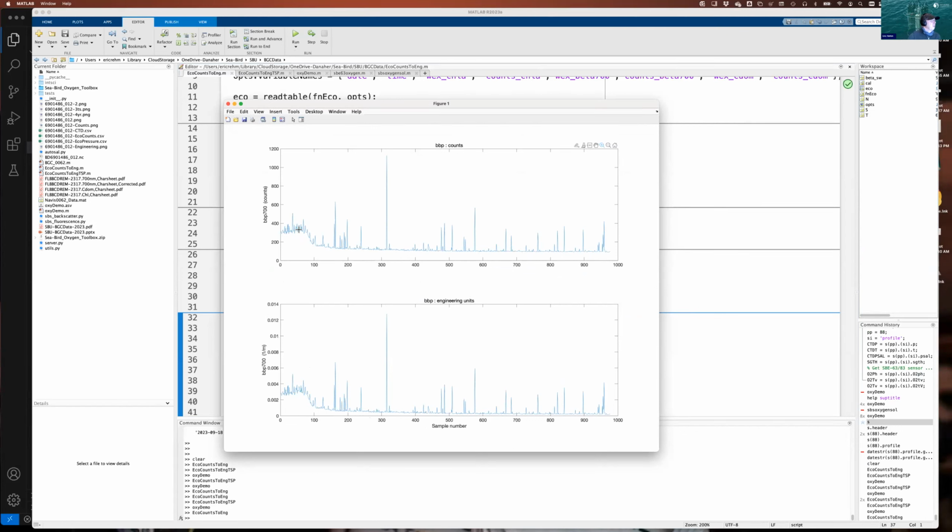If we had 2 different eco units with backscattering, these number of counts might be slightly different due to differences in a resistor or an LED. It's the process of our calibration and those calibration coefficients that guarantees that, whatever changes there are from instrument to instrument, you would always get the same number. So our goal is that if we had 1, 2, or 20 eco fluorometers that had backscattering meters at 700 nanometers, they would all line up on the same axis.